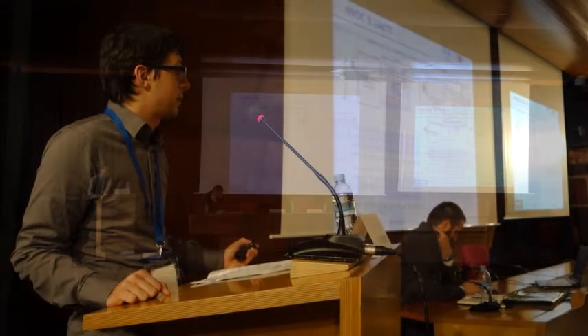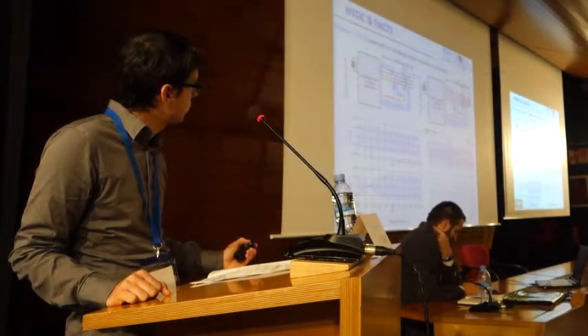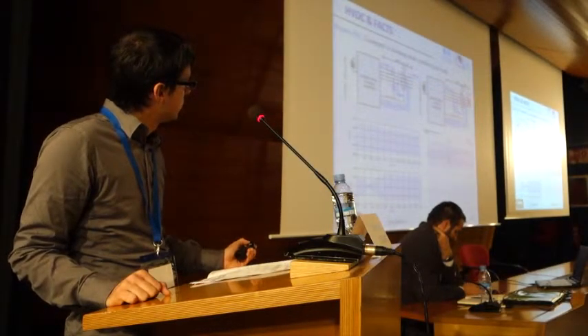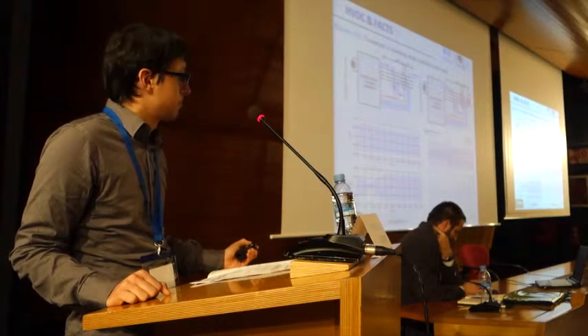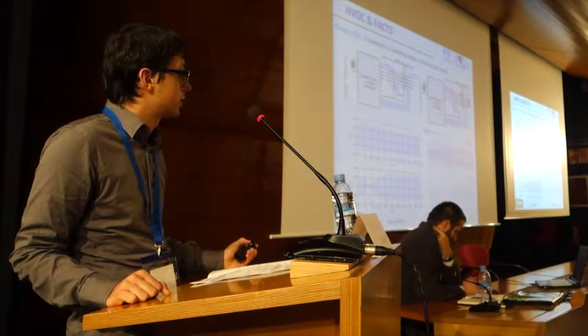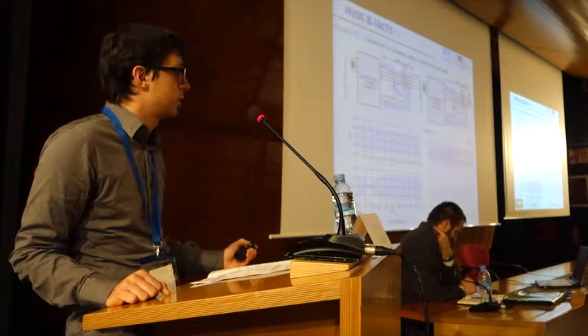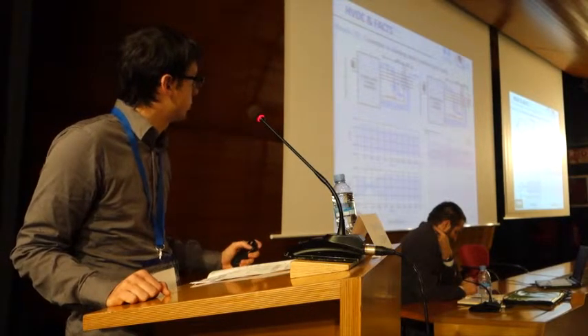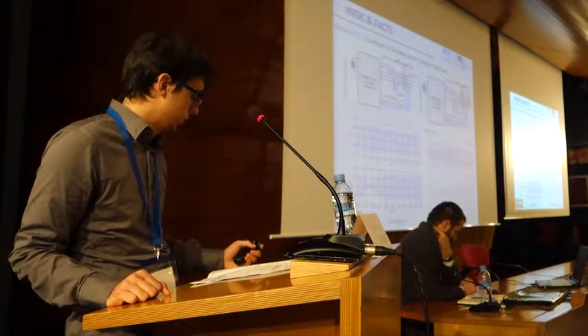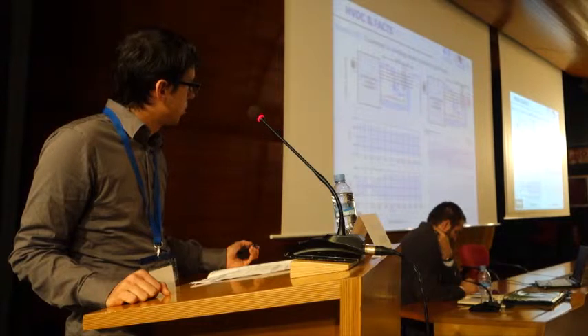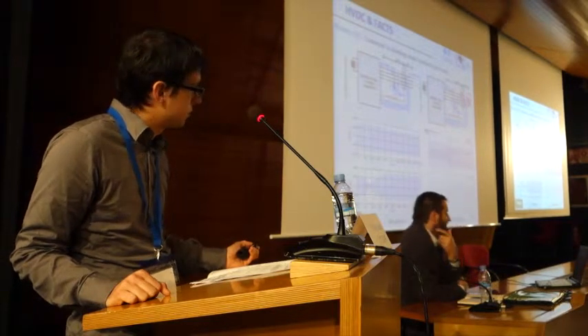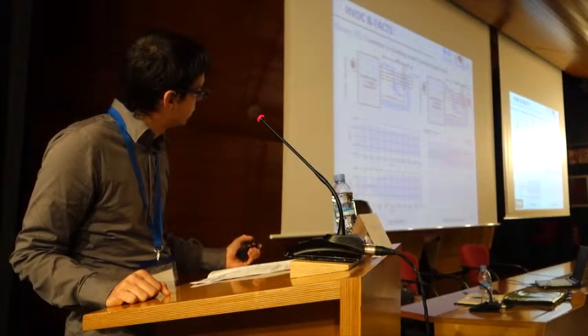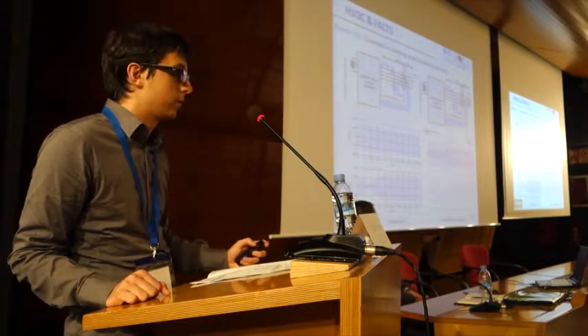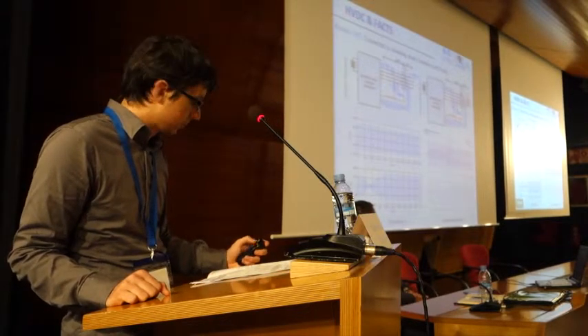And you can see here that, thanks to having a load and a path for the current to be wasted, the voltage is more stable than in the previous case. But the most important thing is that we have a load connected and the voltage is near the nominal value, so it can continue operating, again, without any zero voltage crossing. Here on the current graph, you can see that we go from consuming with a determinate phase to an inversion of phase when we start to deliver the power from the storage system to the local load.